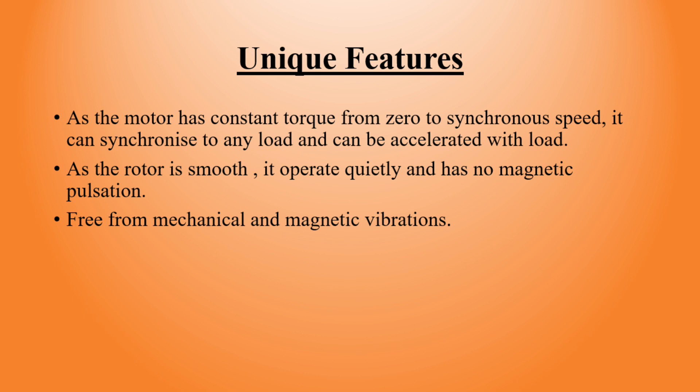As the motor has constant torque from zero to synchronous speed, it can synchronize to any load and can be accelerated with load. As the rotor is smooth, it operates quietly and has no magnetic pulsation. It is free from mechanical and magnetic vibrations.